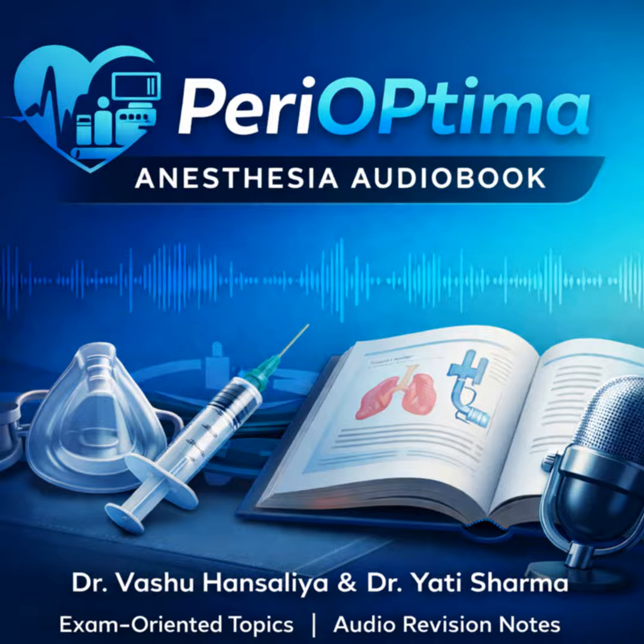The classification, standardized by Mapleson, uses the physical arrangement of just 3 key components relative to the patient connection to define the system's efficiency. The systems are A, B, C, D, E, and F. And the factors affecting that efficiency are purely the positions of those components. The fresh gas inlet, the reservoir bag, and the APL valve. How does their position dictate performance?